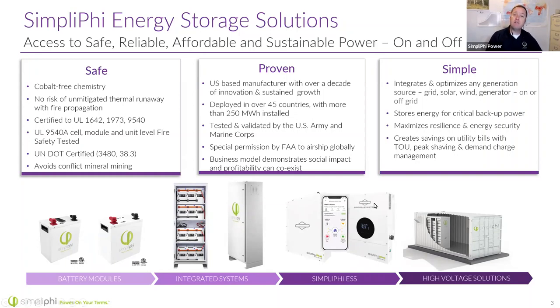We're also excited about our inverter - it's a hybrid inverter with built-in charge controllers and a generator, extra AC input, so you can either AC couple a generator or come out to an existing site. Maybe you've got a homeowner with old IQ6s up on the roof and you don't want to get up there and change them to IQ8s - we can come in and AC couple in a storage system without even getting on the roof, without even touching it.